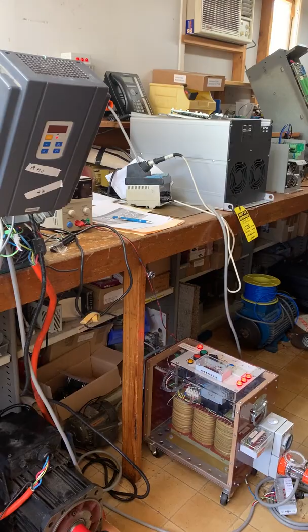Error 15. Okay, so I look up error 15 and I find, yes, error 15 is to do with the pressure transducer being faulty, which I know, I've tried this before. If the pressure is seen to be too high at the start, it thinks that's a major problem. So let's try again. Okay, no error now. So I can ask for a bit of pressure set point. I can tell it to start.